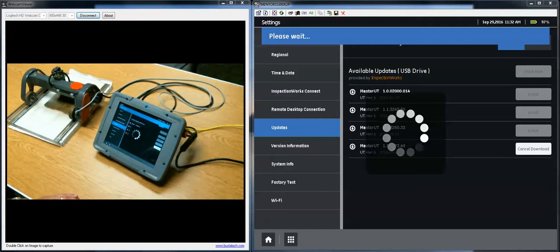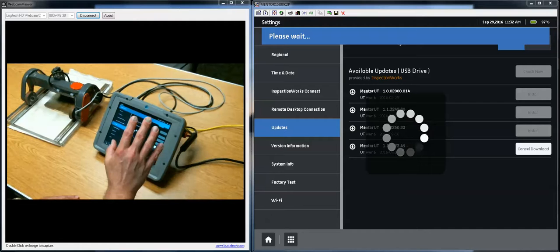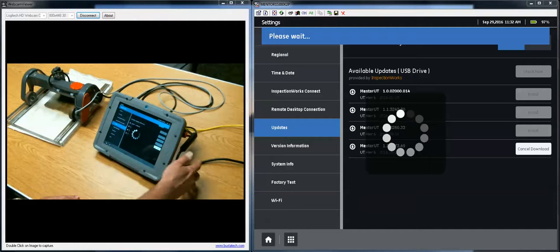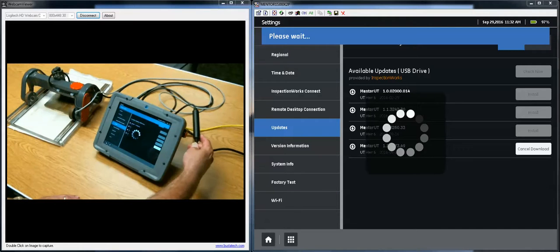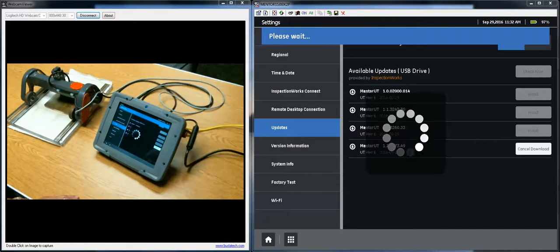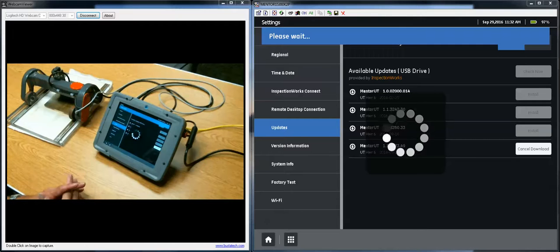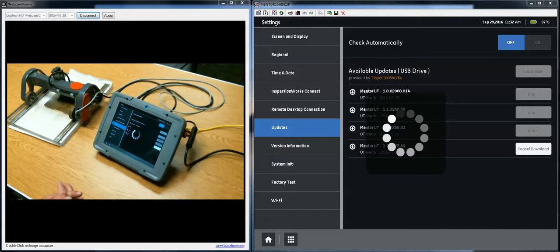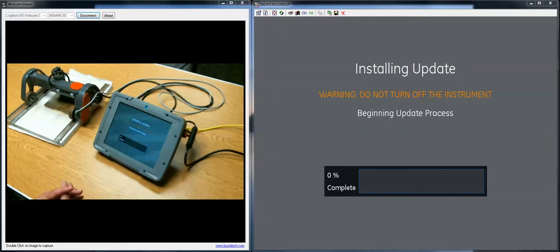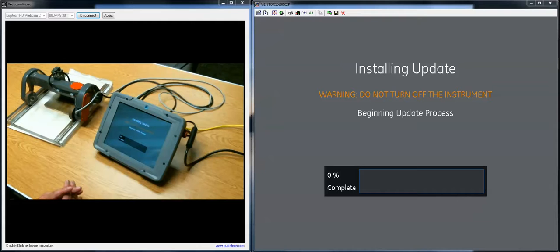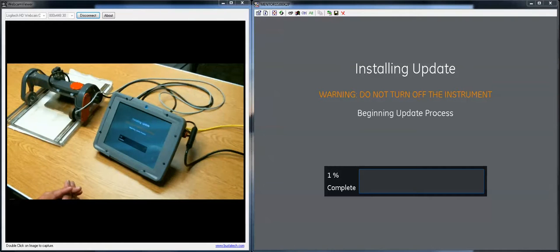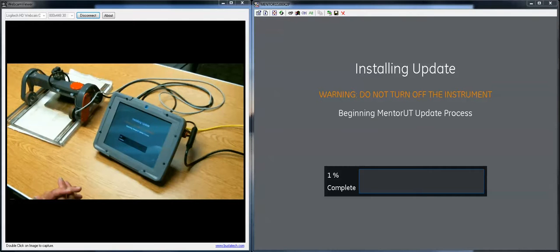It's always a good idea to have the instrument on its charger when you start an update. The update software will check to see how much power is in the battery before it starts. It won't let you start an update with less than I believe it's 15% of the battery charged so that the instrument is confident that it has enough power to complete the update process.